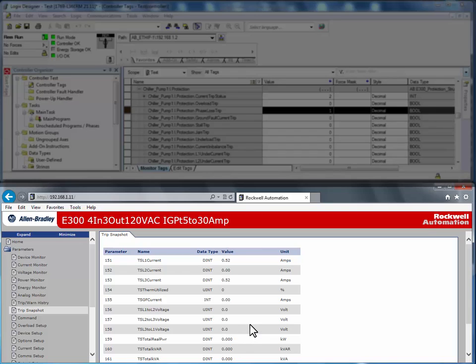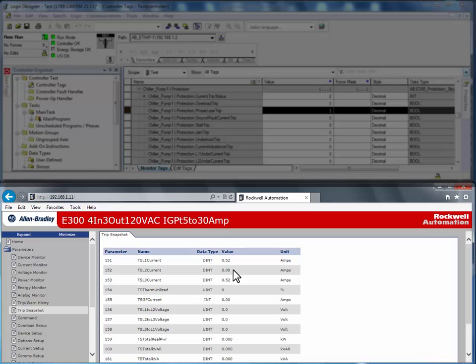In this example, L1 current was at 0.52 amps, and L3 current was at 0.52 amps. Unfortunately, L2 was at 0 amps. This is the reason for the phase loss trip.